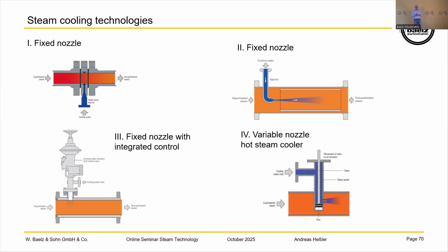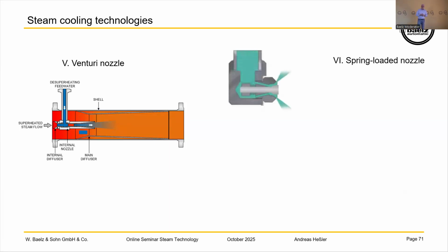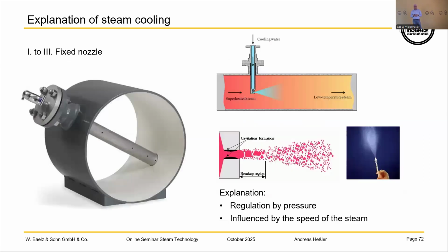The next one would be a variable nozzle, meaning we have different kinds of nozzles with different kinds of KVS that we open and close. Another technology would be a Venturi nozzle, and a spring-loaded nozzle would also be a technology. And last but not least, a motive steam cooler, which uses motive steam to vaporize the water droplets and make them very fine. I just want to explain the different kinds of cooling systems and what they are doing.